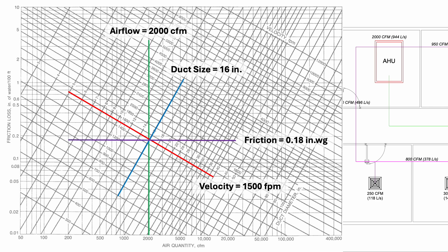According to the equal friction method, this will be the friction loss value that we use to size the rest of the duct. We can also reverse the process and use 0.1 inch water gauge as the primary factor to size our duct. Just be sure the velocity does not exceed the recommendations.